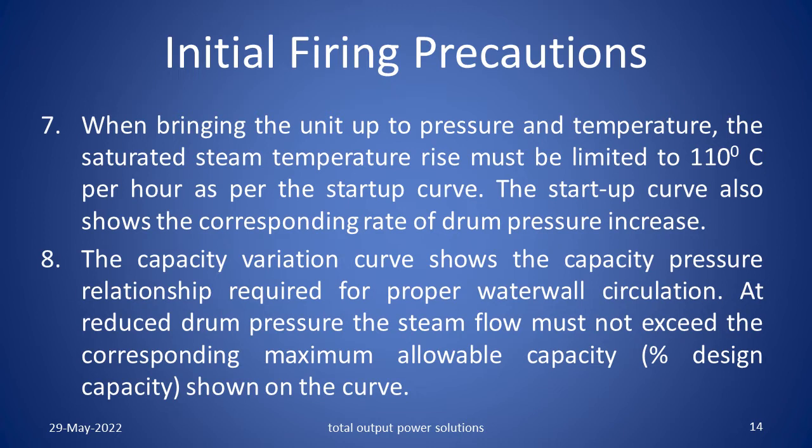When bringing the unit up to pressure and temperature, the saturated steam temperature rise must be limited to 110 degrees centigrade per hour as per the start up curve. The start up curve also shows the corresponding rate of drum pressure increase. The capacity variation curve shows the capacity-pressure relationship required for proper waterwall circulation. At reduced drum pressure, the steam flow must not exceed the corresponding maximum allowable capacity, i.e. percentage design capacity as shown in the curve.